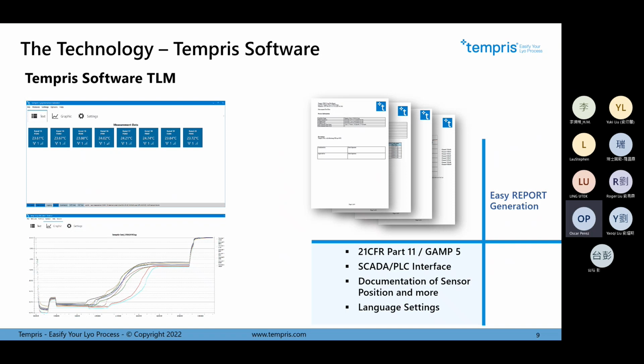We have different licenses for the software. It shows the temperatures in real-time monitoring, shows which antennas are catching each sensor, shows the sensors with their serial numbers, and shows the complete cycle that we are measuring, all in real time. We can export and manage this data during the cycle as well, for example to a CSV file while the cycle is running. Everything can be complemented with additional software licenses and documentation. We can integrate these signals into the freeze dryer control system via Modbus, Profinet, Ethernet/IP, as well as 4-20 milliamperes, the traditional wired signal.